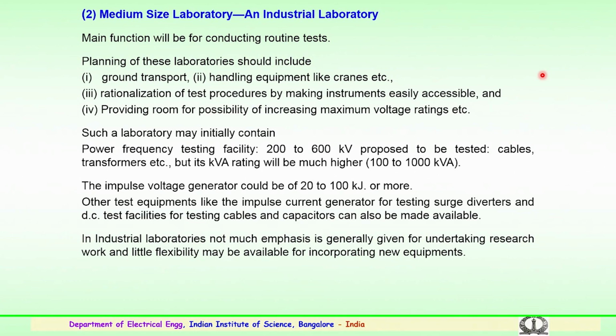And in medium sized laboratories, the impulse voltage generator could be of 20 to 100 kilojoules or sometimes could be higher. So, other test equipments like the impulse current generator for testing of surge arresters or diverters, and DC test facilities for testing cables and capacitors can also be made available in such medium sized laboratories. Normally in industrial laboratories not much emphasis is given to undertaking research work, and little flexibility may be available for incorporating new equipments. So, this is generally used for routine testing on the products manufactured in a particular industry.